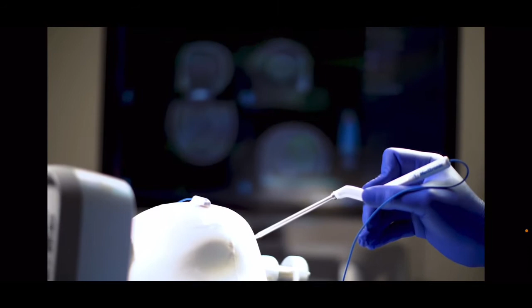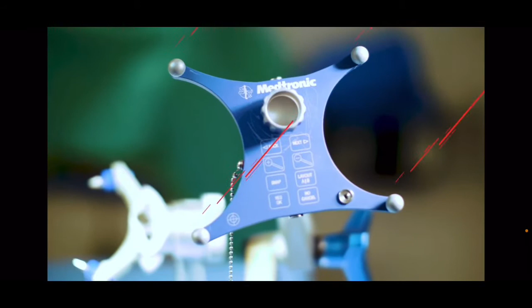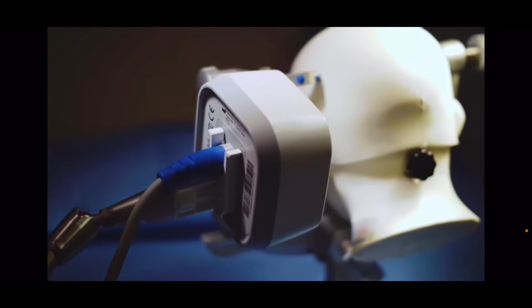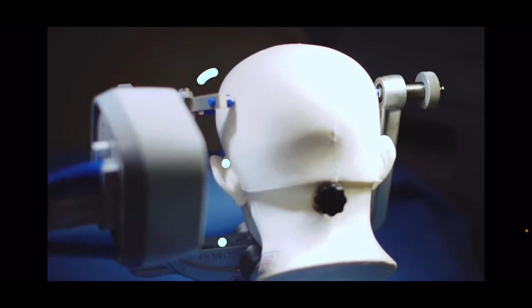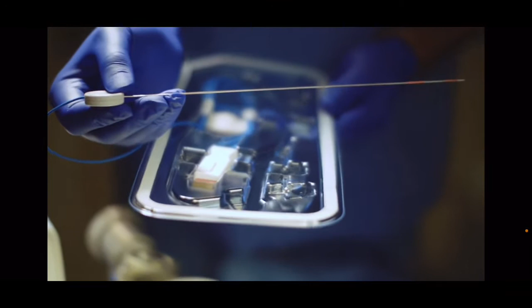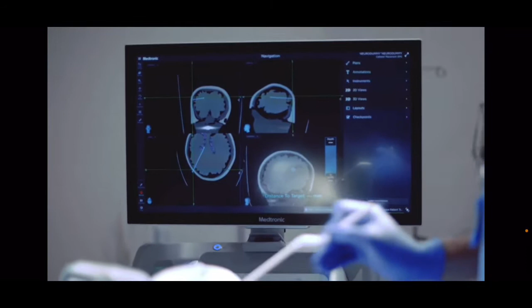The system can track instruments either optically using an infrared camera or electromagnetically. With optical tracking, this camera sends out and then detects infrared light that's reflected from these silver balls. The camera then transmits the instrument's location to the navigation software. Similarly, with electromagnetic tracking, the emitter emits a low-energy magnetic field with unique characteristics at every point. The electromagnetic instruments contain sensors, which allow the navigation software to identify the instrument's location within the electromagnetic field.